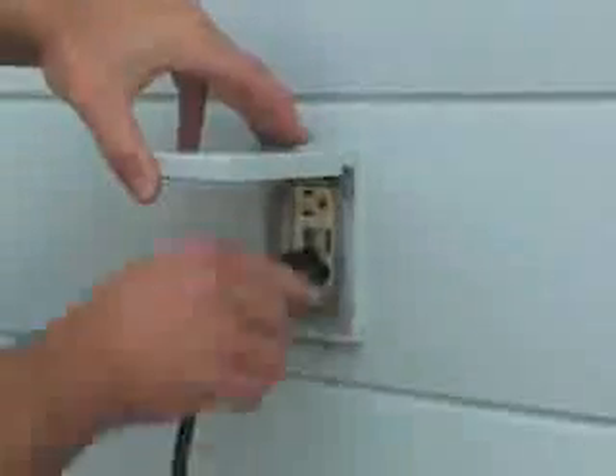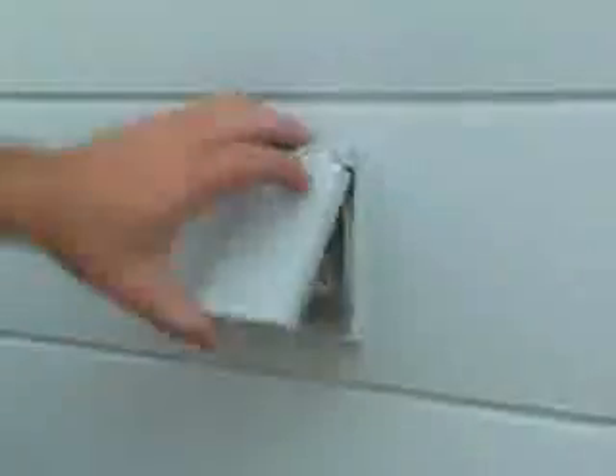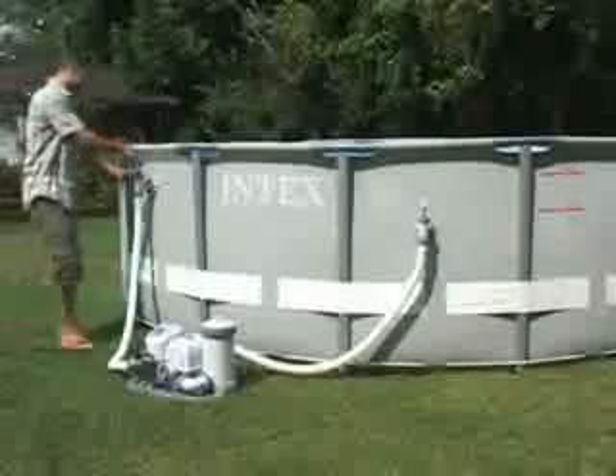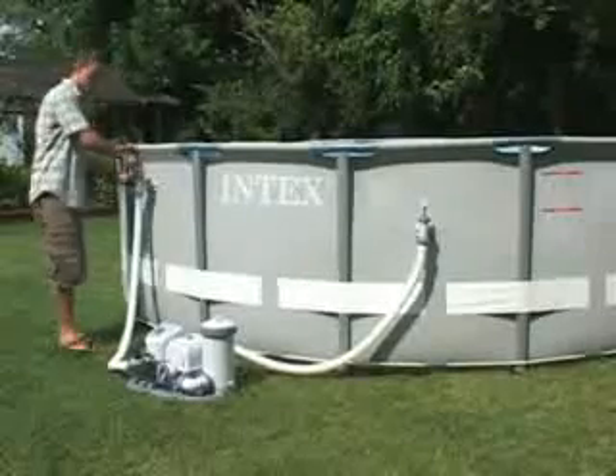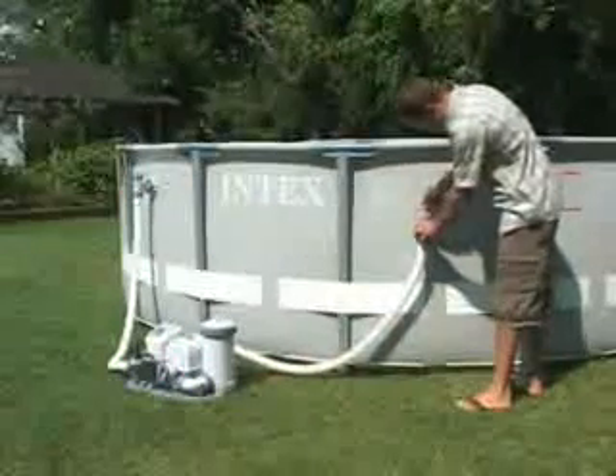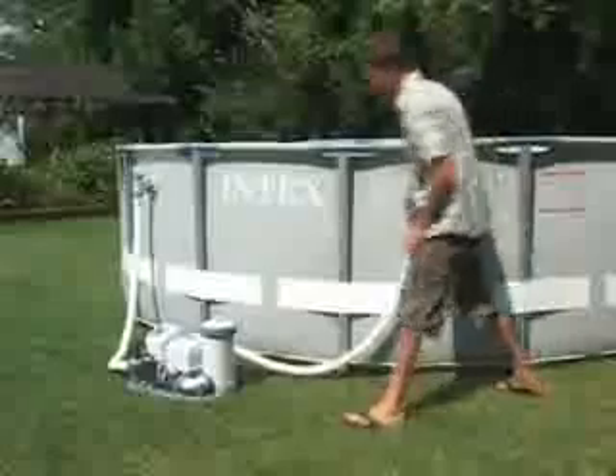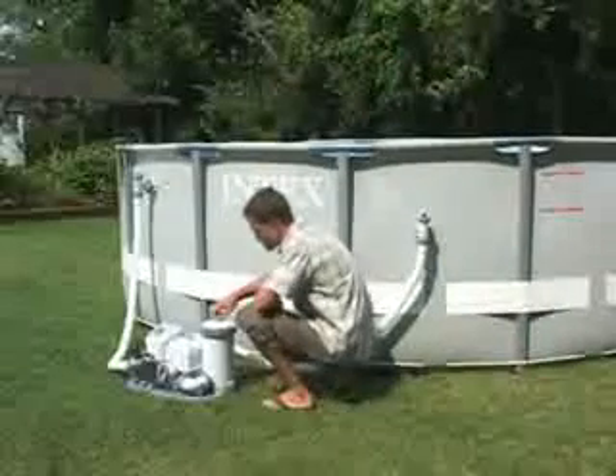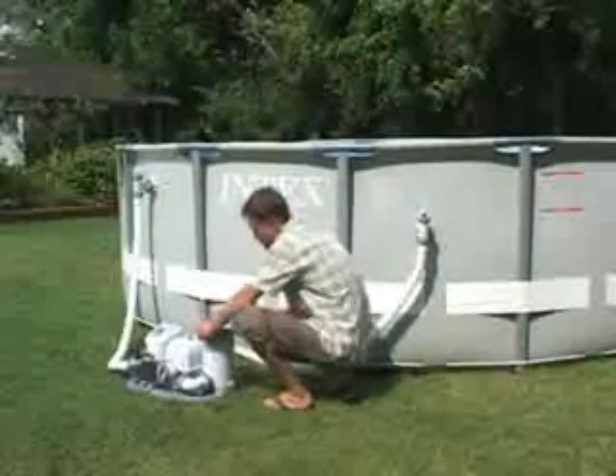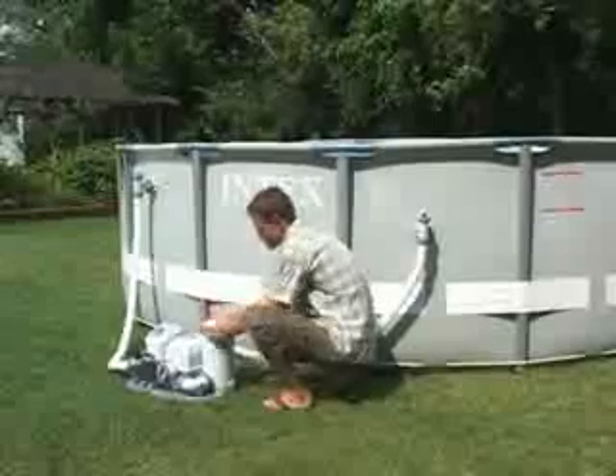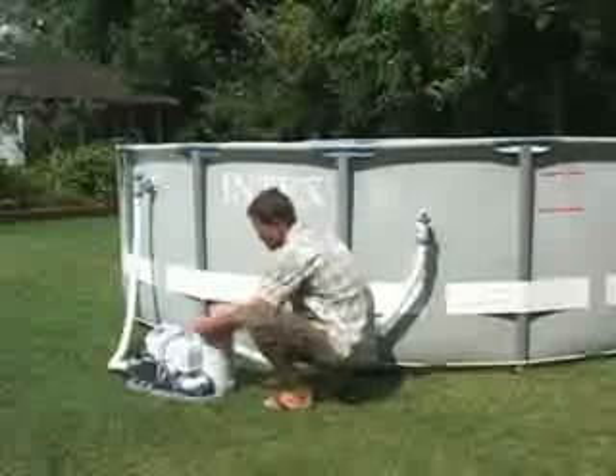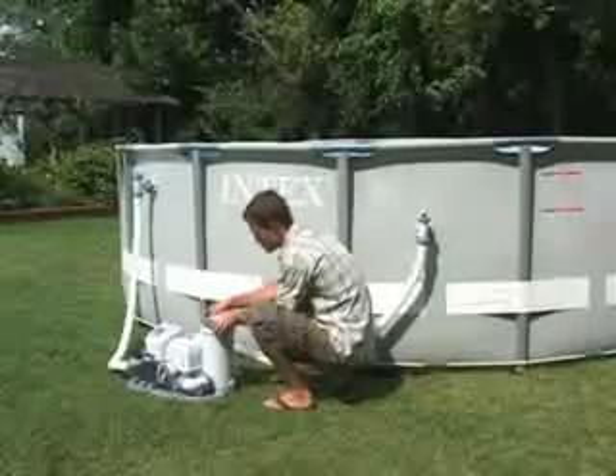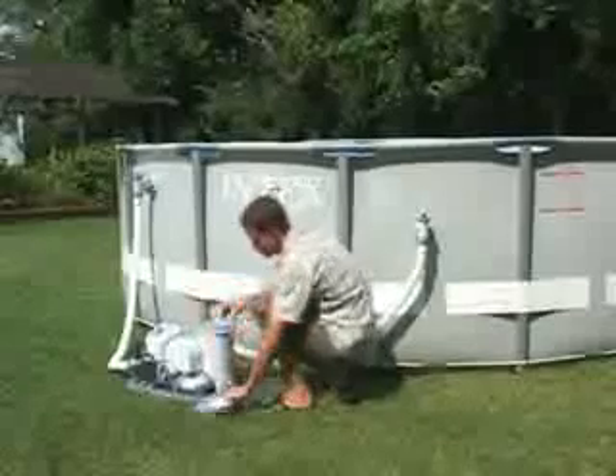At that time, check to see if it needs to be replaced. First, unplug the electric cord, then close both plunger valves. To make it easy to remove the filter housing collar, open the air release valve on top. Release the filter top collar with a counterclockwise rotation, taking the top and the filter cover off. Then, lift the cartridge out.